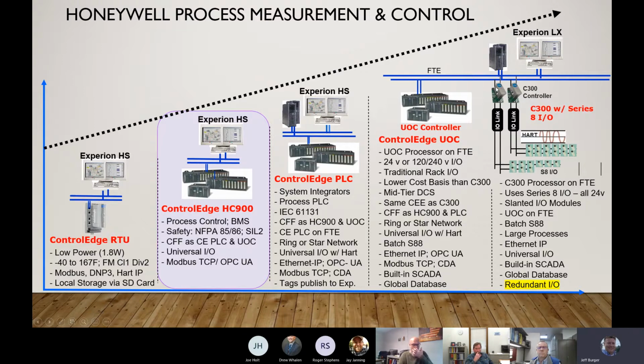You can see the C300 I/O cards up here on the top where my cursor's hovering over. The C300 is a true DCS system that again is used a lot in the large refineries, chemical facilities, pharmaceutical, sometimes in power gen, but these are distributed control systems that have I/O through the entire plant, and with a common SCADA system which is called Experion LX, which is basically the Experion HS on steroids. So it's a very large system, SCADA system that can control an entire plant. On these larger systems, instead of just having the CPU as a redundant, it also has the I/O architecture redundancy built into it as well.